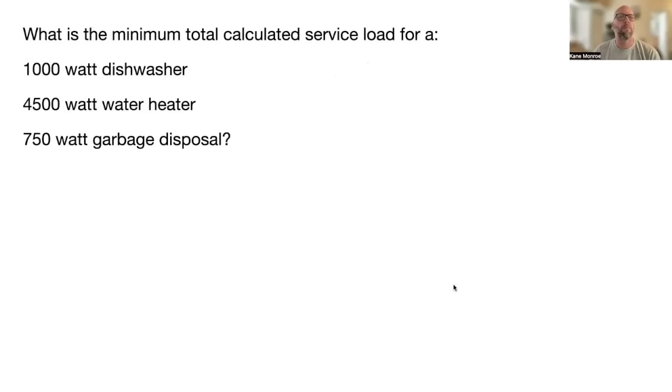What is the minimum total calculated service load for a 1000 watt dishwasher, a 4500 watt water heater, and a 750 watt garbage disposal? Remember, it's less than four or less, so we don't have to multiply times 0.75. We add those up and it comes to 6250 watts. NEC 220.53.